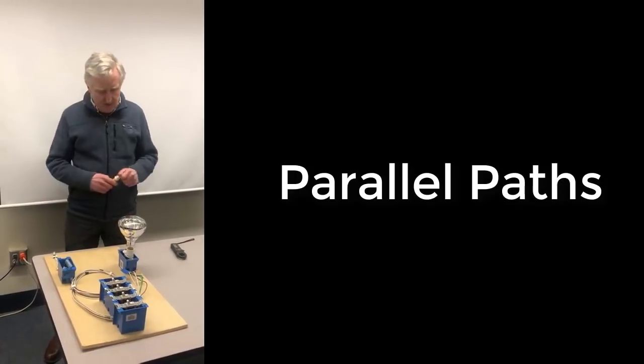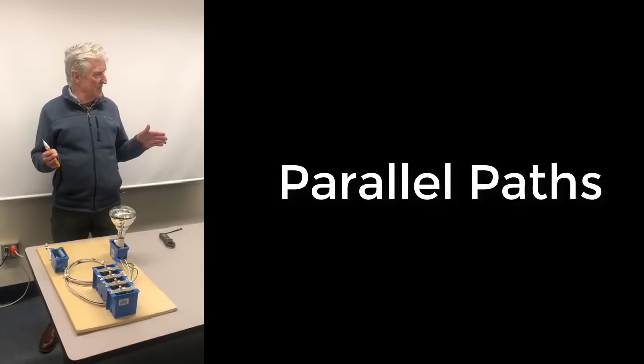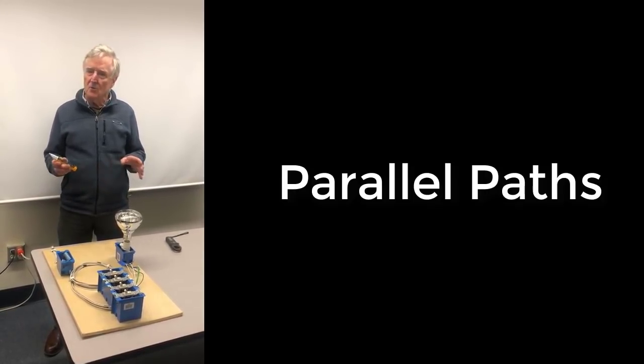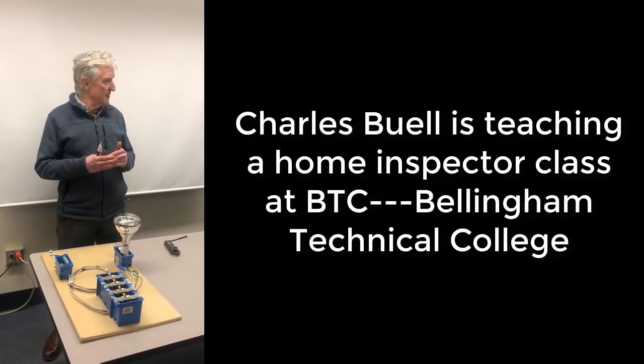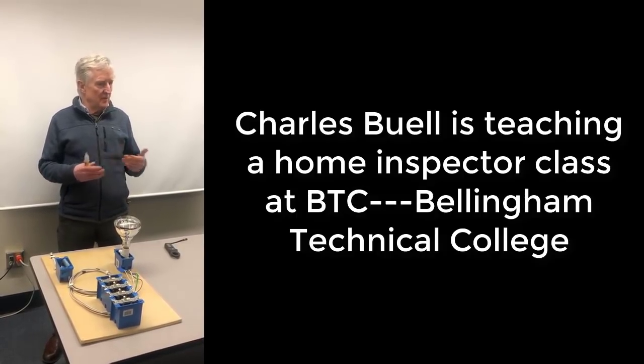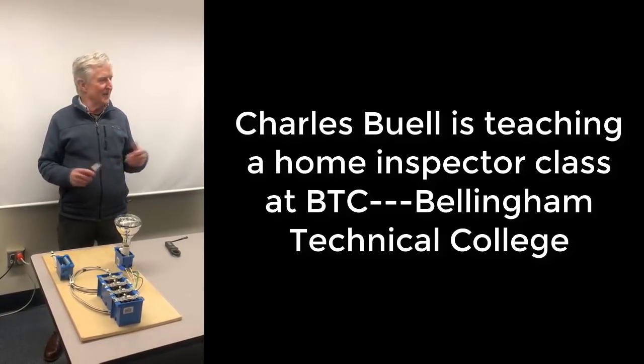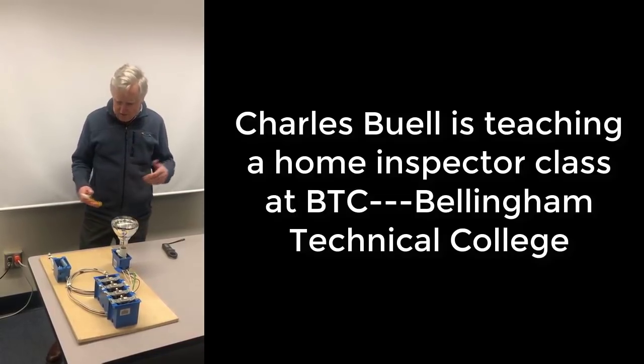So with this demonstration, we're going to talk about parallel paths. And really, the story behind this is why we don't connect the grounds and neutrals together in a subpanel. This is always perplexing the inspectors: why can't we? I don't understand the problem. So I'll show you what I've done here.